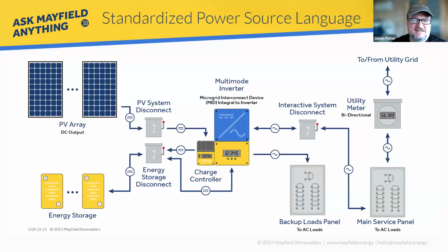But this question of what happens on the energy storage system side is another really important thread that hopefully you'll see be noticeable throughout 706. A lot of the language has been deleted, so it won't necessarily look like something major was changed, but a lot of language was deleted that should be covered by the listing. That's the long answer: if you're talking about means of disconnection or isolation inside of the listed energy storage system, that should all be covered under the listing, meaning it should be addressed in the installation instructions and the information provided by the manufacturer, because that's your best way of proving it's covered under the listing. You should have some relief there, and hopefully 706 is going to add less confusion into those discussions.